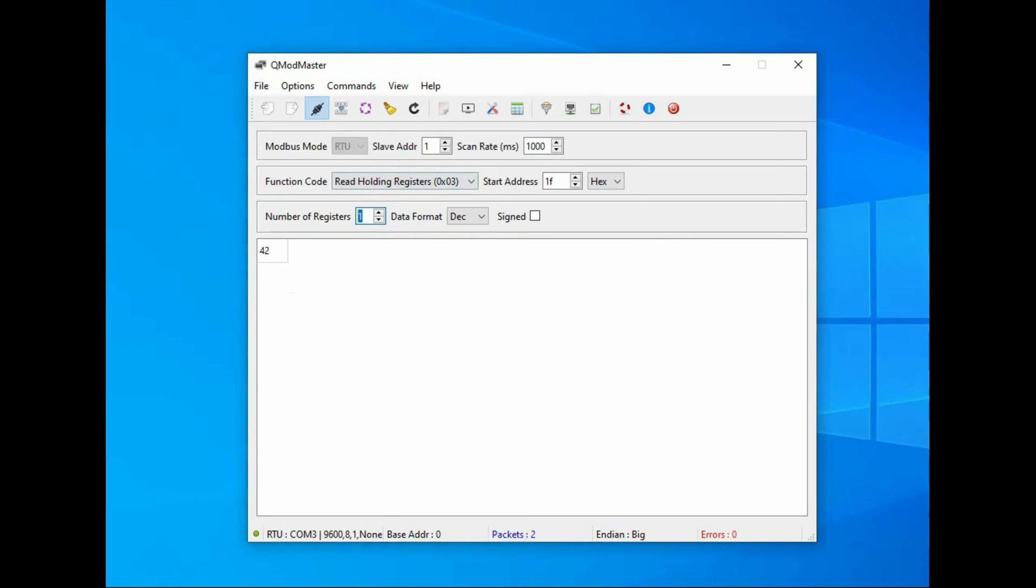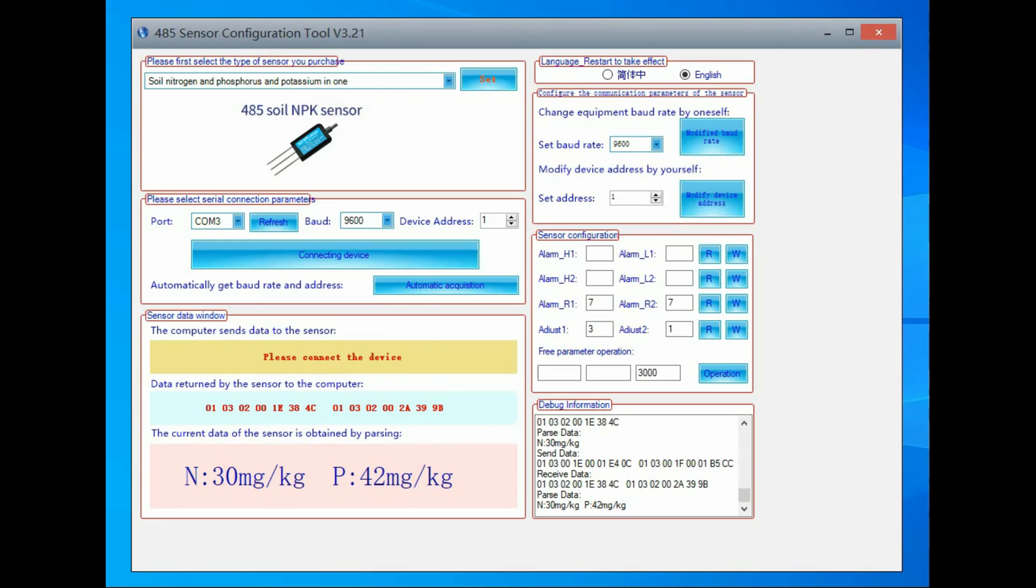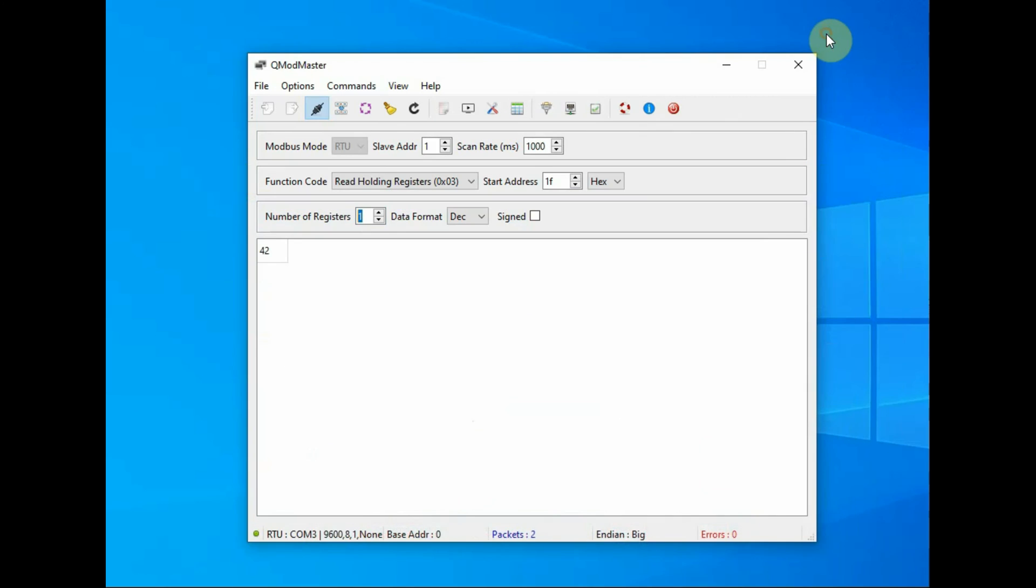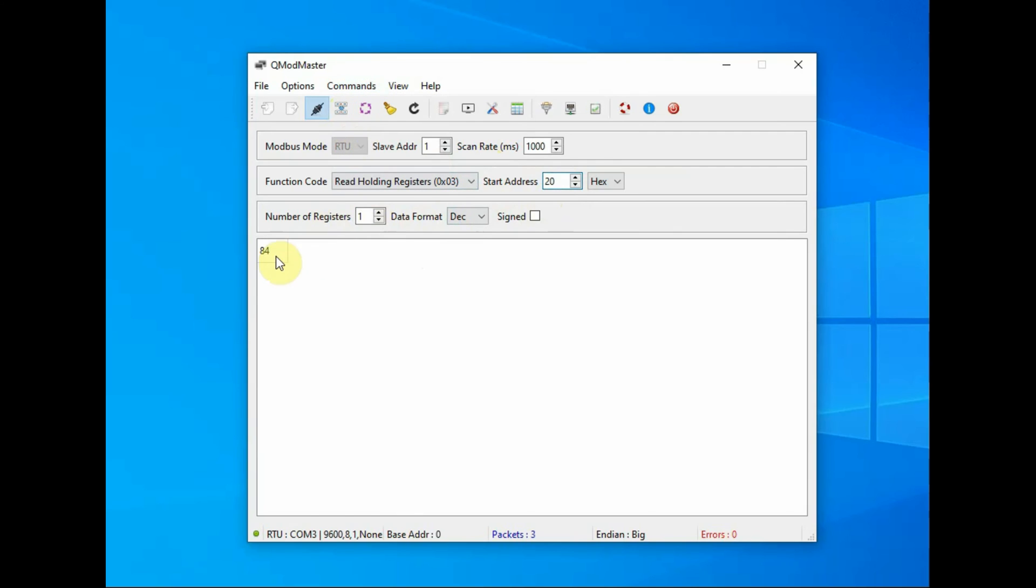Same way, change the start address to 0x20, you will get the potassium value. So this is individual register reading. Now let us read all the three registers starting from start address 0x001E, next is 0x1F and the third one is 0x20. So start address is 0x1E and number of registers is 3, so you will get three positions.